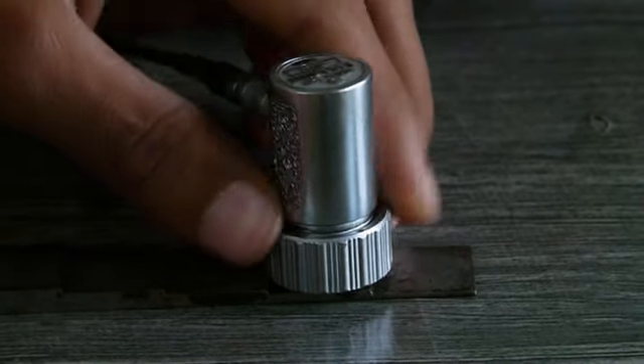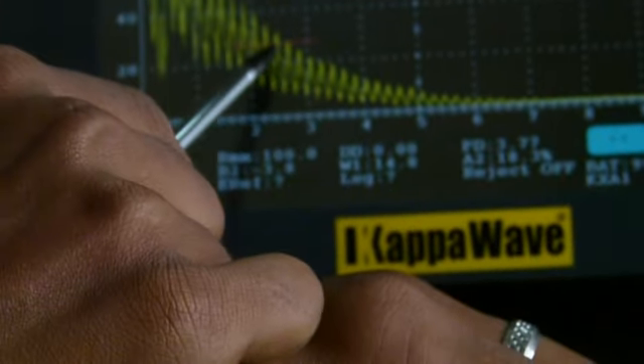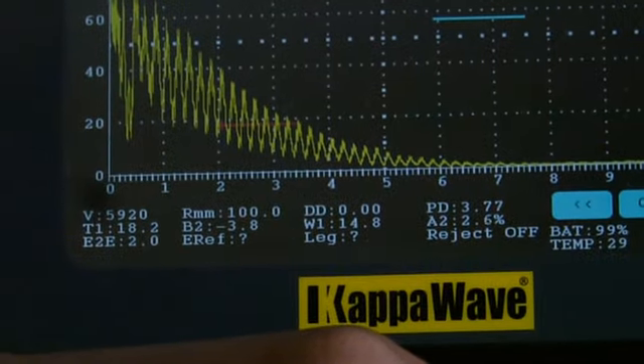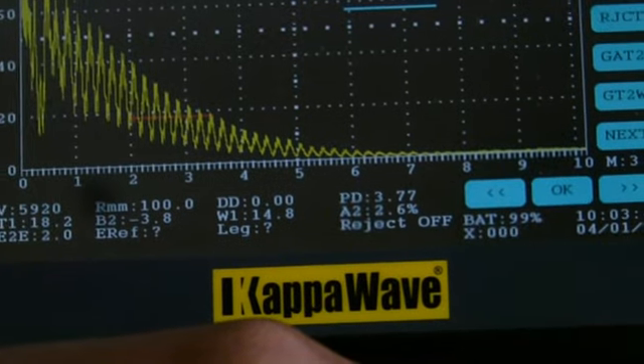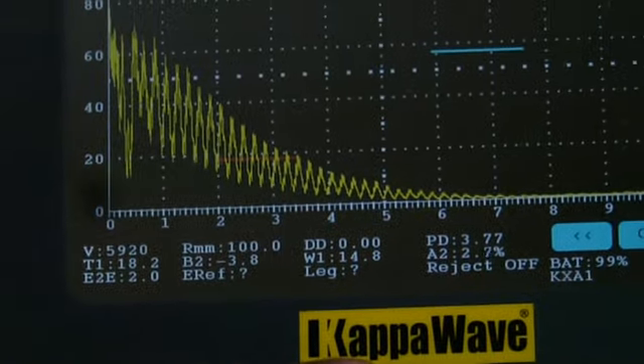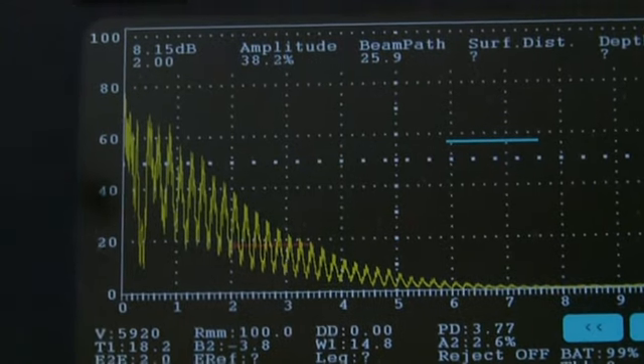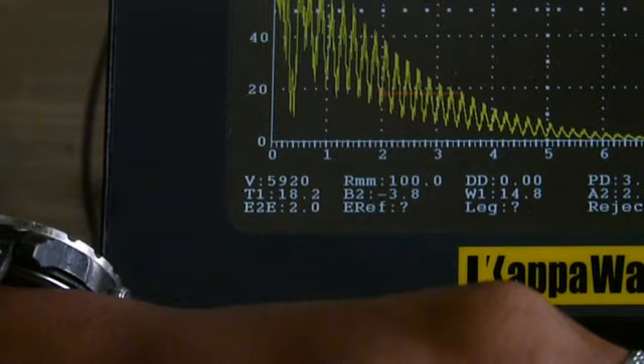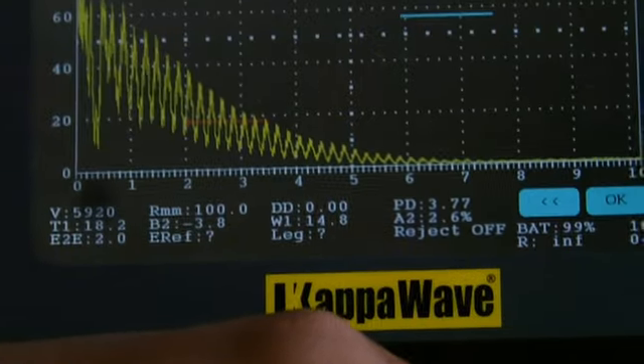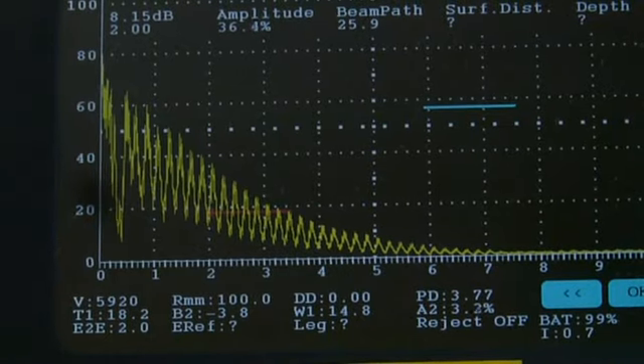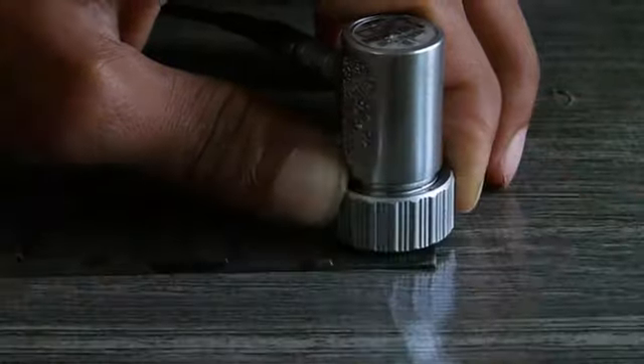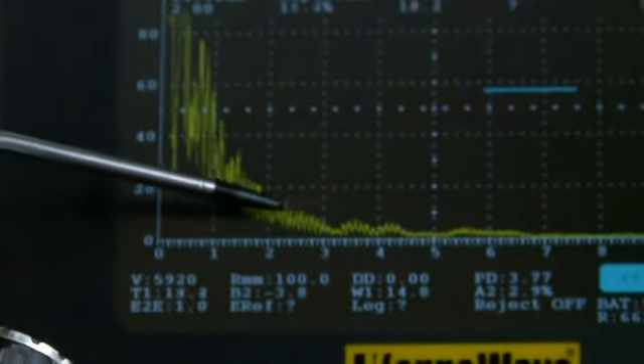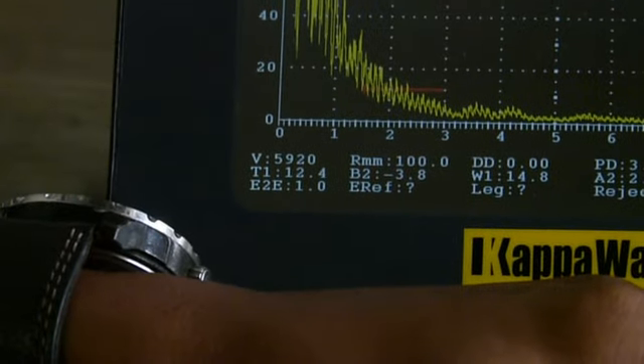We'll go to 2 millimeter thickness now, and we are using a standard 4 megahertz normal beam probe. And here the echo to echo value is read as 2 millimeter. Using the same probe, we will now proceed to measure 1 millimeter on the same step block. Place it on 1 millimeter. We are on 1 millimeter now. Let's see whether we can read this 1 millimeter clearly. So echo to echo can be read as 1 millimeter.